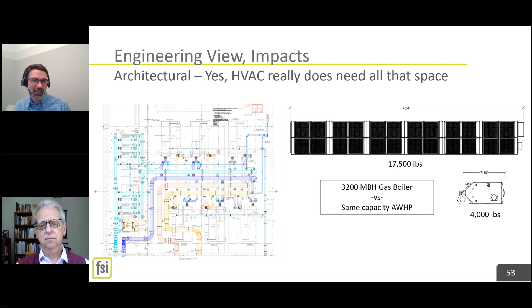Yeah, this building's kind of a crazy one because we have an air to water heat pump, but then we also have a chiller plant because it's life sciences. So we were going to have a chiller plant no matter what. This chiller helps the chiller plant, but it doesn't make up the chiller plant. But this is, again, an oddball. In a standard office building, you could do a 2-pipe changeover, so you're not running 4 pipes, savings, and you can run your chiller in the summer as a chiller, and you can run it in the winter as a heater, and you don't have double the equipment. So Duane's point is valid, occupancy dependent, but talk to your engineer about what you're going to need to do for this.